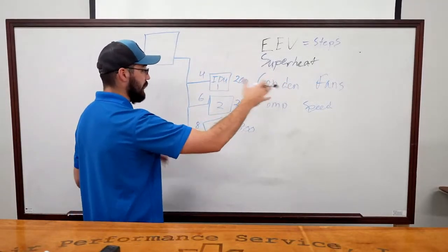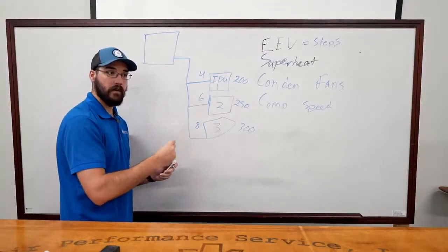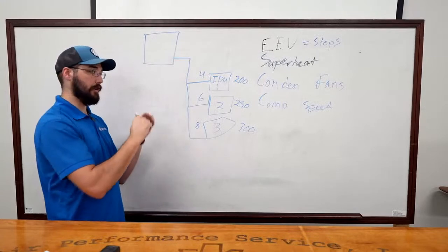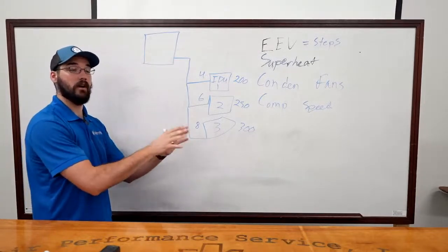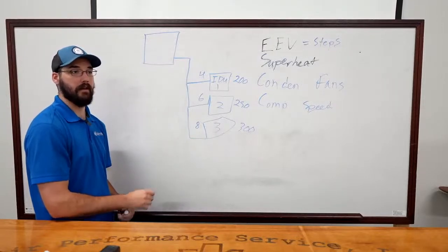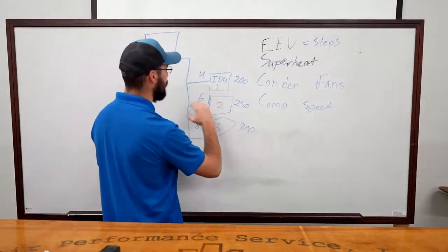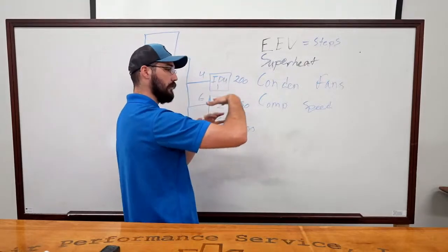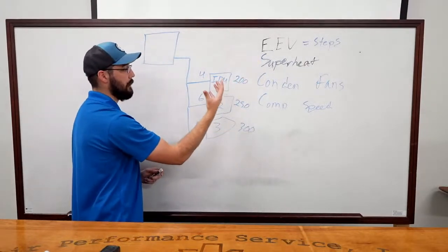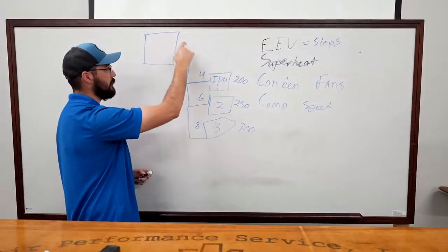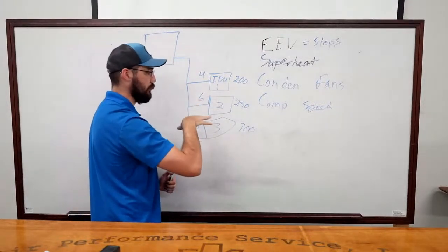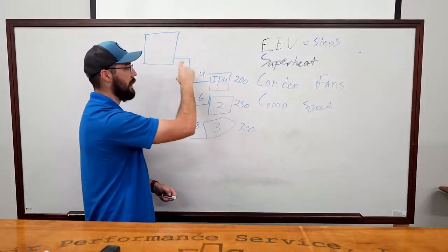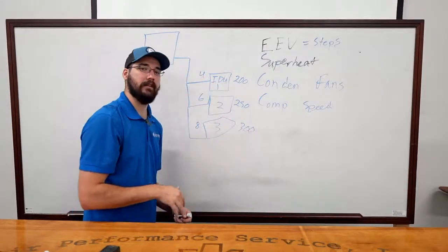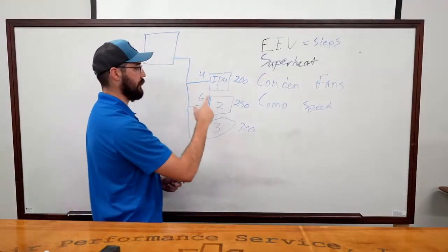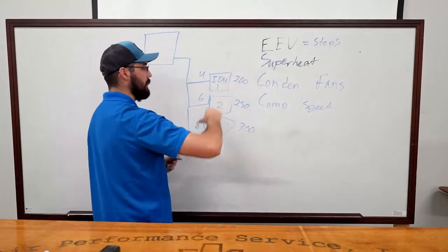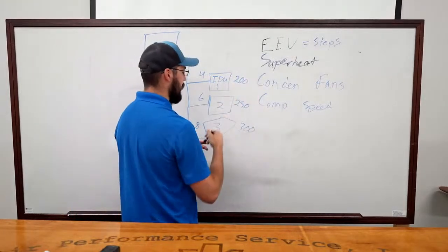So we give it 10 minutes. Now this is something you're not going to just turn on and be able to get a diagnosis. You're going to have to turn it on, step back, and let it run for at least 30 minutes. It takes that long, because this system is going to slowly ramp, slowly build, and try to get that capacity. Part of what it can do is store up enough of the refrigerant before it loads itself that it'll be able to maintain, at least from the computer side, for the first little bit. But you'll notice that the longer it runs, these values are going to slowly climb.